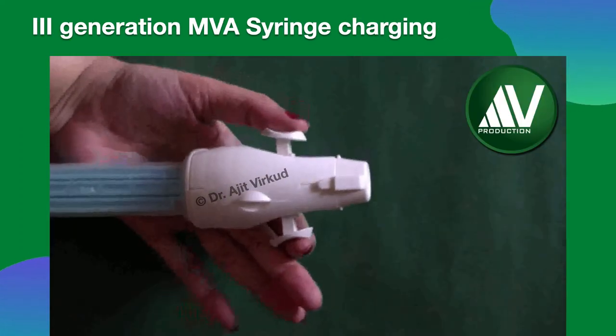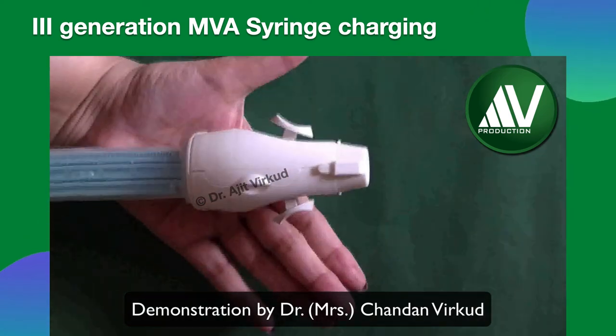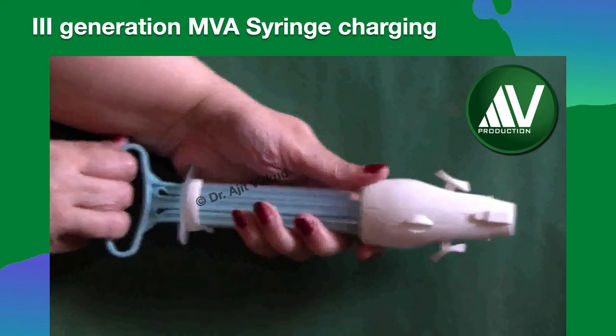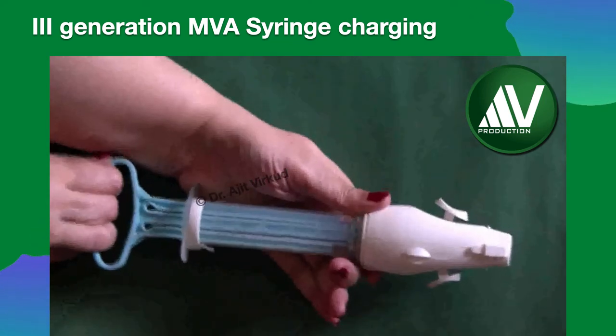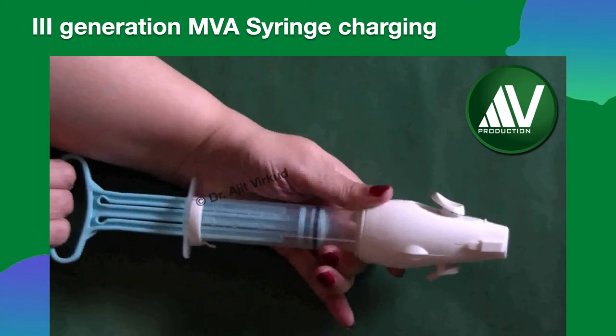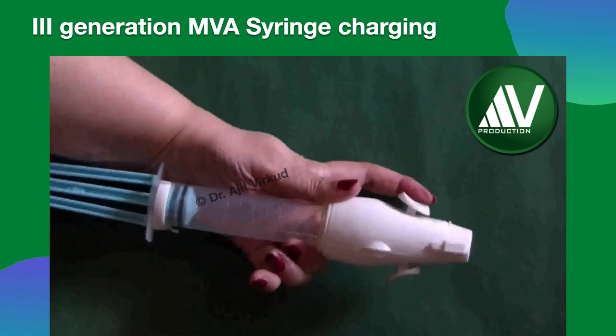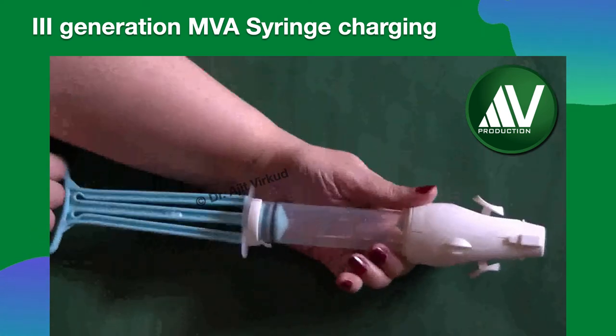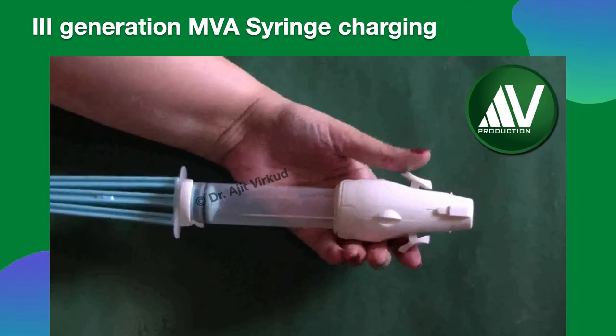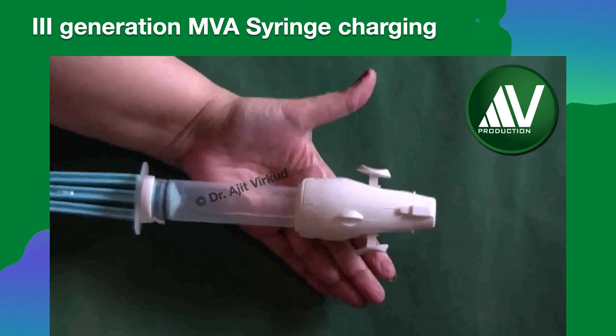A video demonstrates how to charge the Ipas MVA Plus syringe to create vacuum: push the valve buttons down and forward until they lock, then pull the plunger back until the arms or flanges snap outward and catch on the cylinder base. Check vacuum by leaving the instrument in the charged position for 2-3 minutes, then release the buttons. A rush of air indicates that the aspirator maintained vacuum.